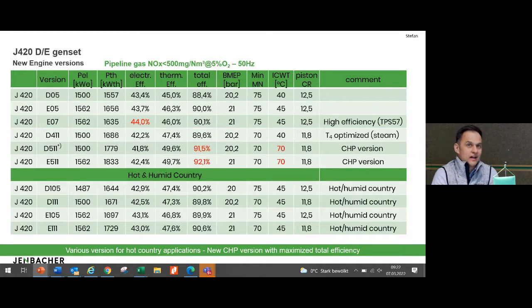Okay, apologies. Now coming to the performance data of the new engine. As you can see here on this page, we have collected the most important versions there for 500 milligram NOx and 50 Hertz. I will not go through the entire table, but I want to point out here 4 specific versions. One is the E07. This is our high efficient version of the 420 with the TPS 57 up with an electrical efficiency of 44%. We have as well done a version for steam optimized. So this means we have the D411 with the highest exhaust gas temperature optimized as said for steam production. And we have implemented there 2 CHP versions.